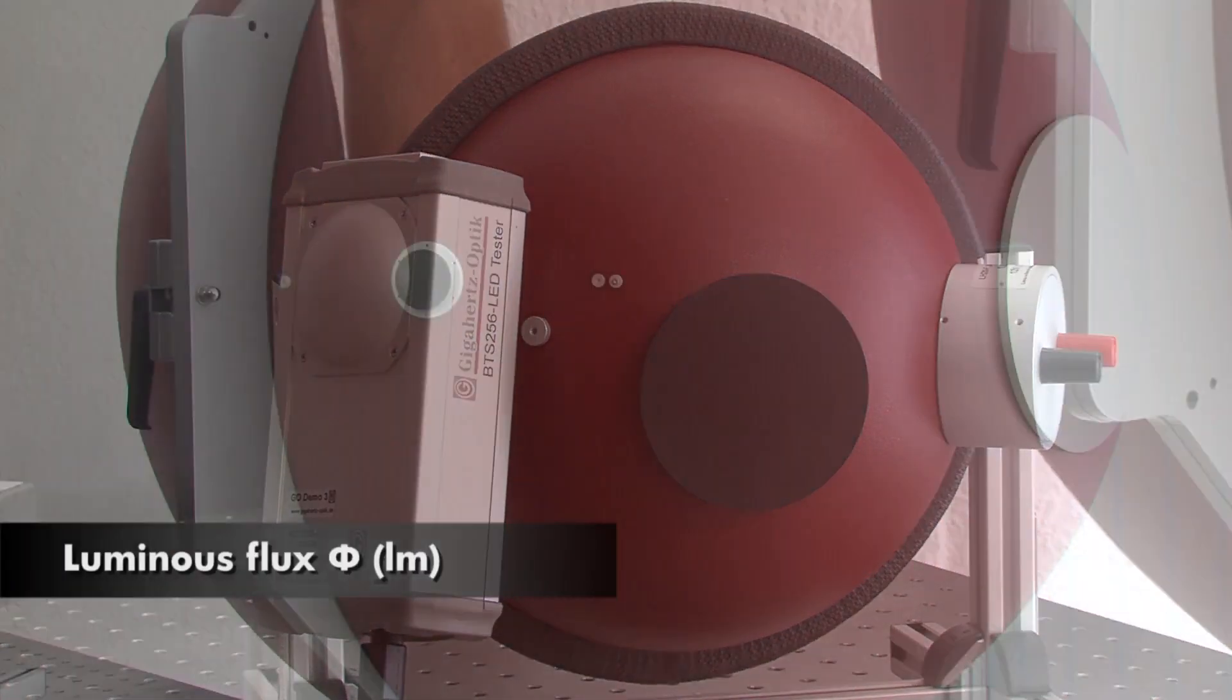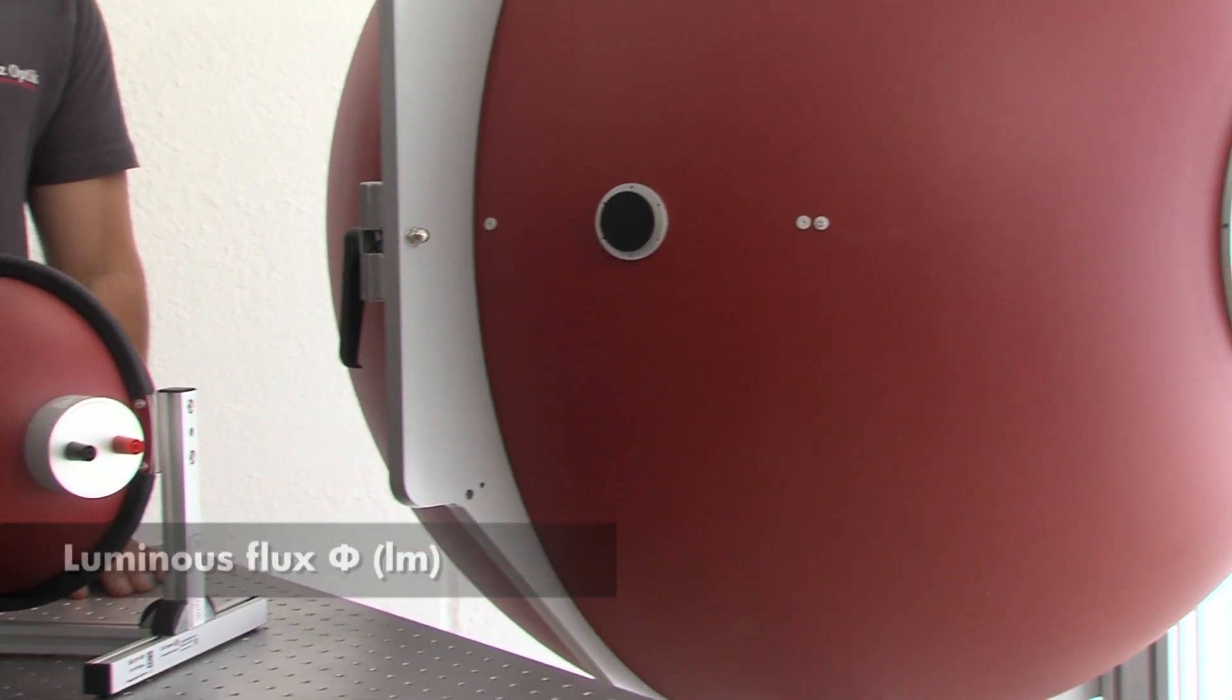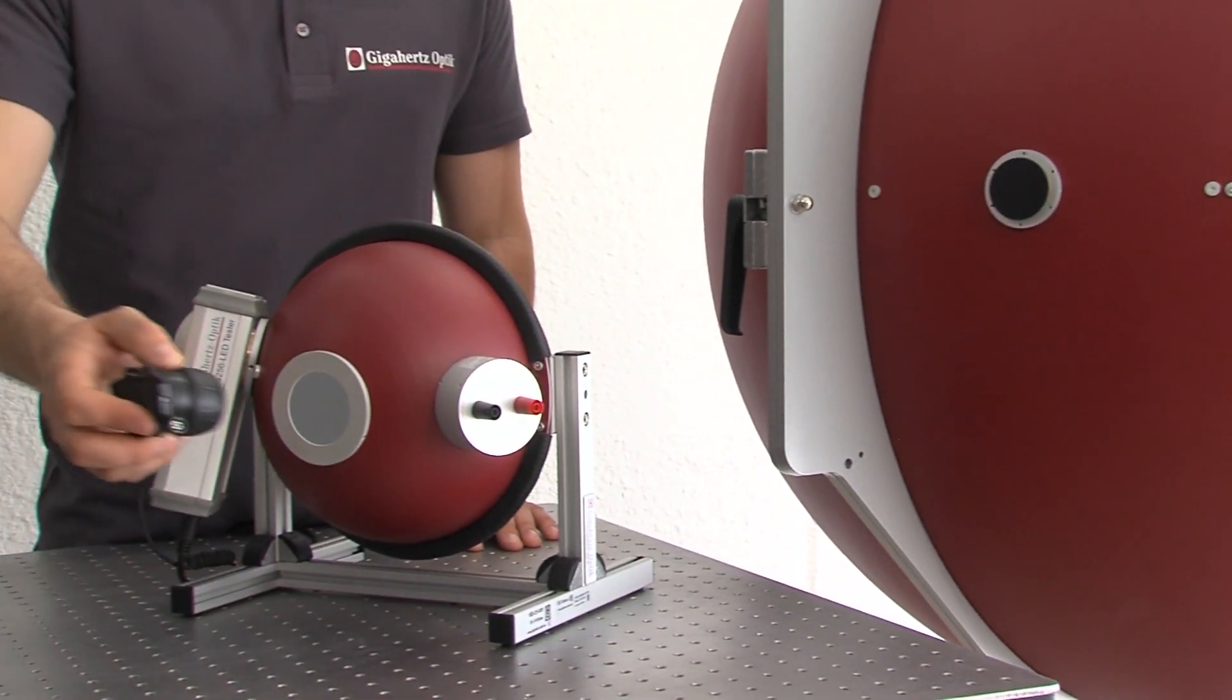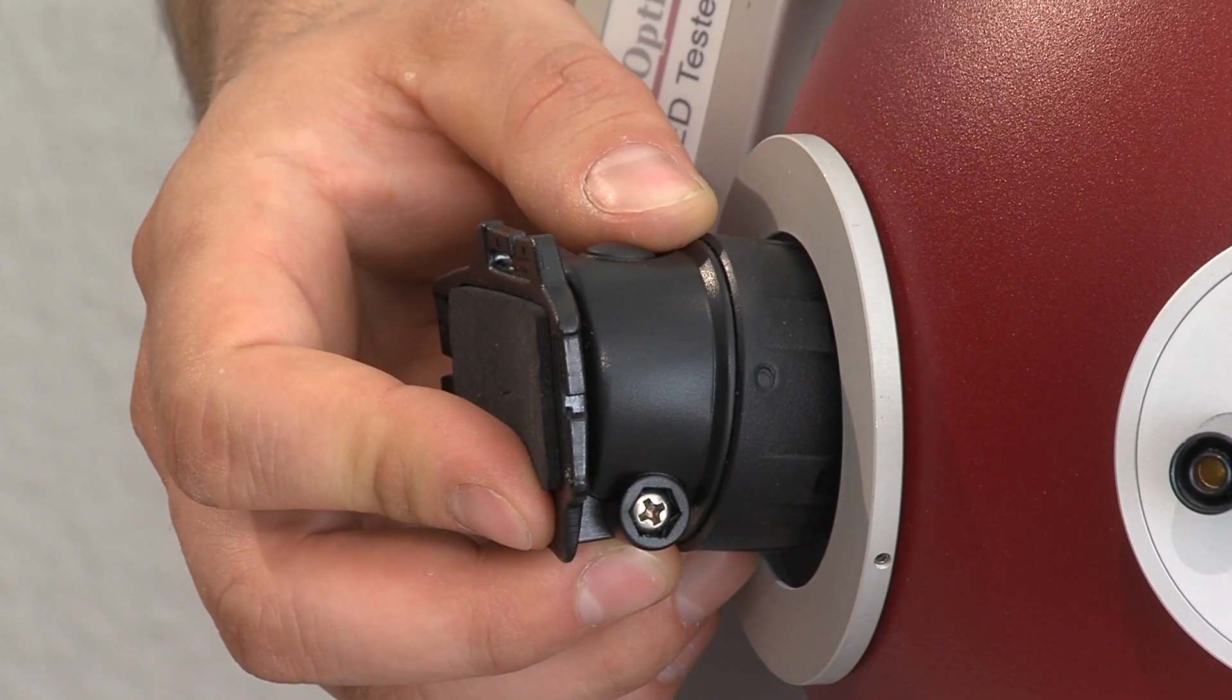For luminous flux and luminous color measurement, the LED matrix or spot source must be mounted at the light input port of the integrating sphere so that all of the light enters the integrating sphere.